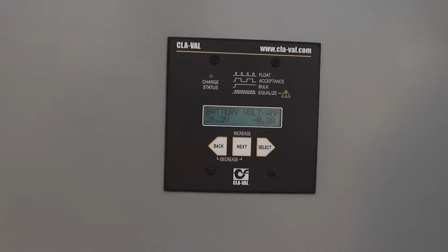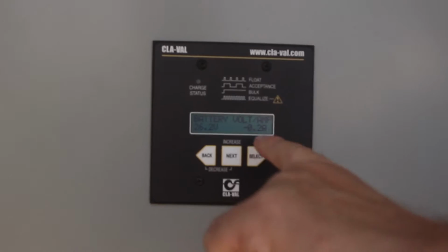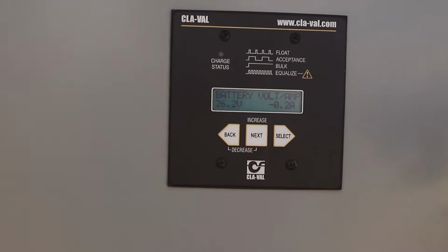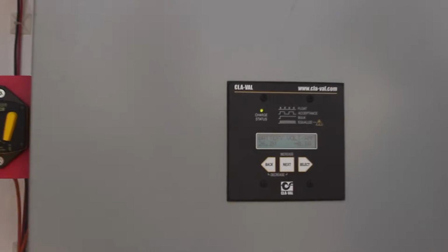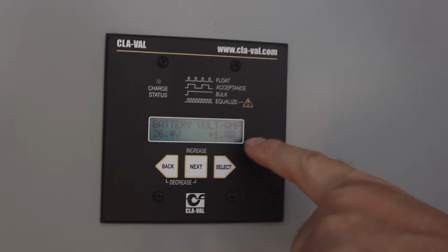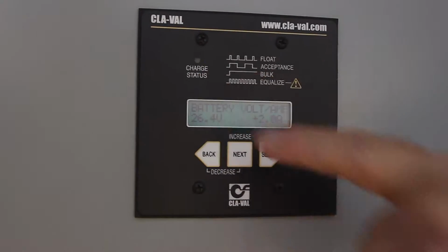its part. And by the way, the less the differential, that may explain it. I just noticed we're not actually running. We probably lowered our differential below the minimum. So right on camera, we actually prove that the generator does need 25 to 30 psi pressure drop. So as he increases the pressure drop, this should start kicking into a positive. In fact, it's starting to flash. Now it's going positive.